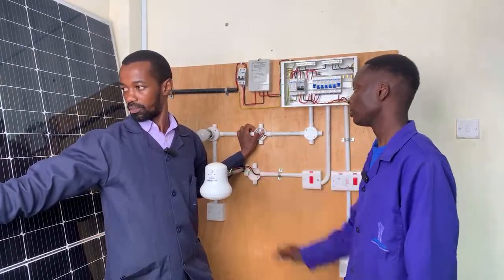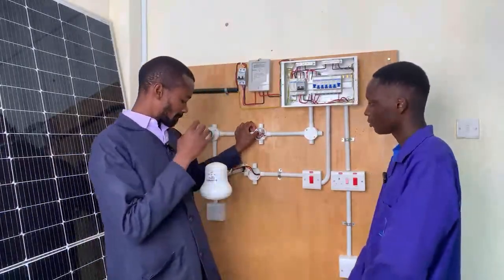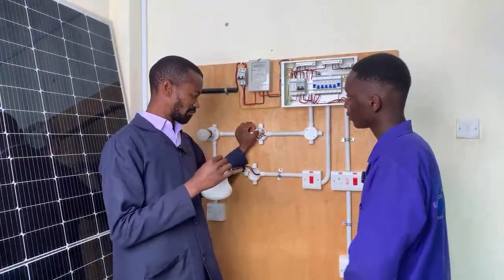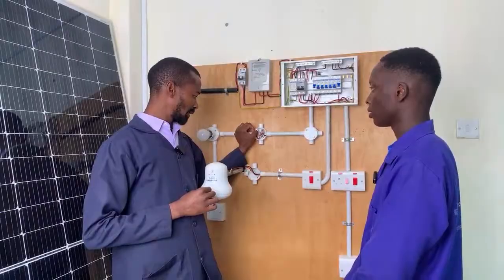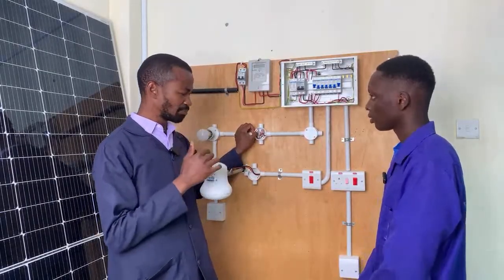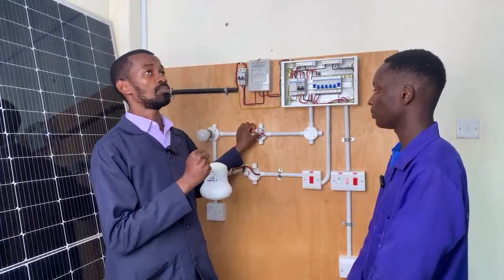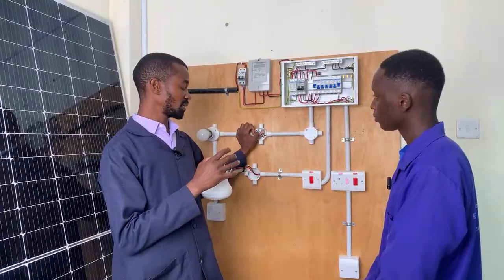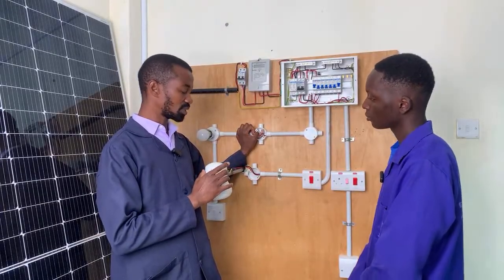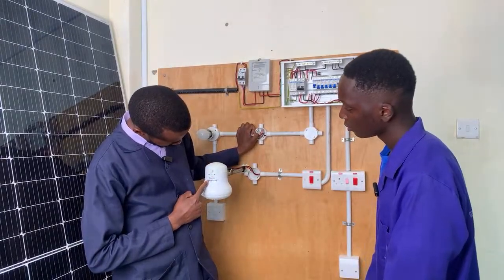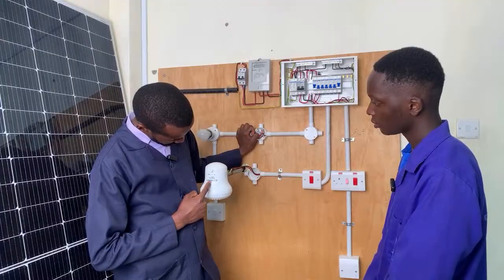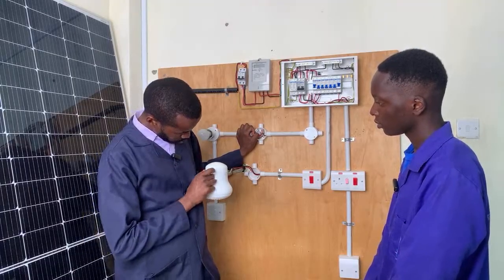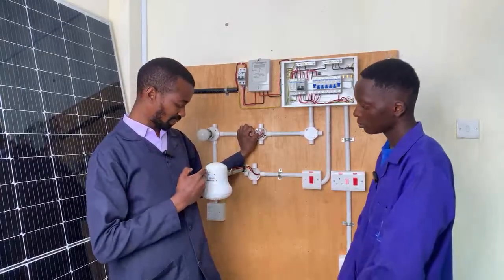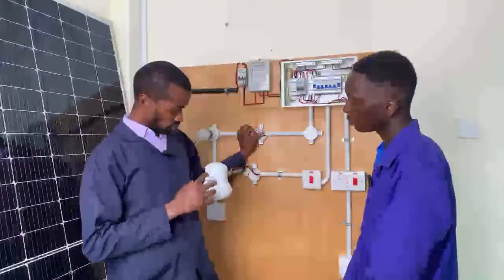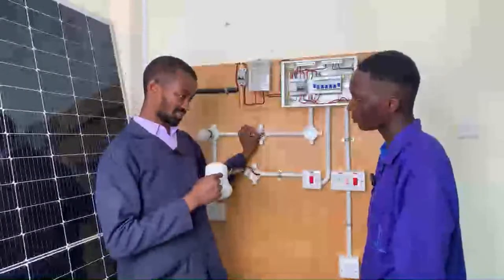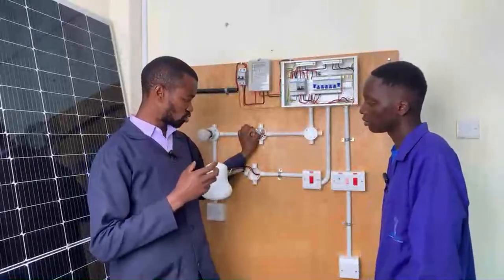For me, I would think a 2.5 mm would actually work, but the problem is the cables will start getting warm. What I've also seen in many cases is that this instant shower head gets replaced with a bigger one. For instance, this one is rated at 4600 watts, 25 amperes. In most cases, when you select the hot setting, which heats water the most, it switches all the way up to 5600 watts. That is a lot of power drawn from the circuit.